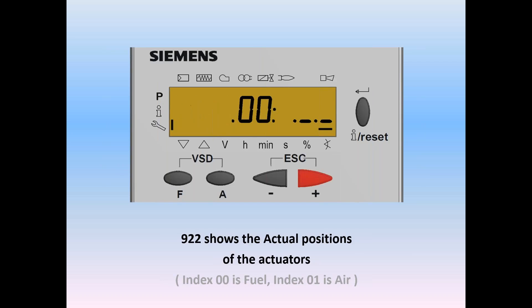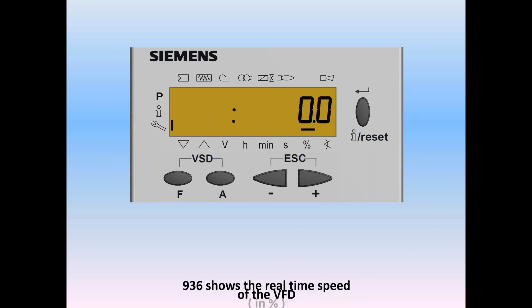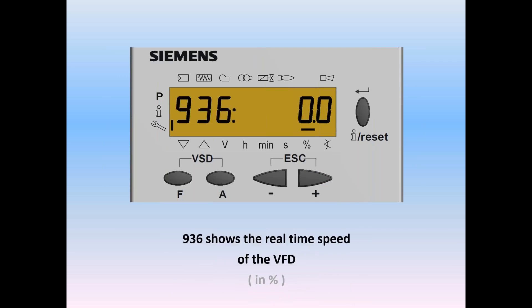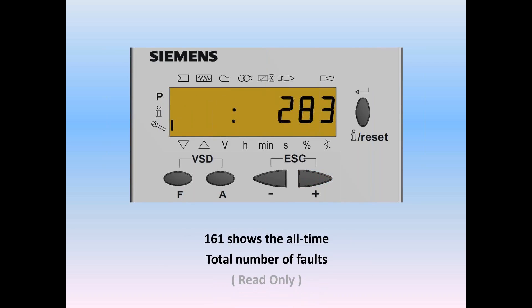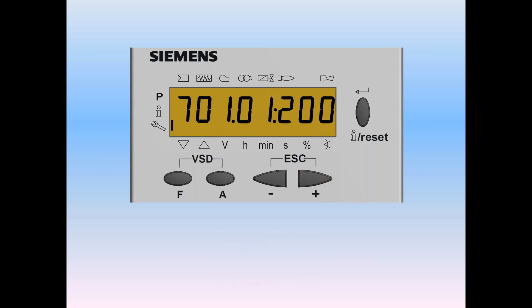Do a plus and we get 936, which shows the real-time speed of a VFD if equipped — in this case it's 0, with the bar above the percent sign confirming 0% VFD. Do a plus, and parameter 161 shows us the total number of faults — it's read-only. It tells you this system has experienced 283 faults in its entire lifetime. Do a plus, and here we are in the 700 series, which is the fault history on the LMV3.